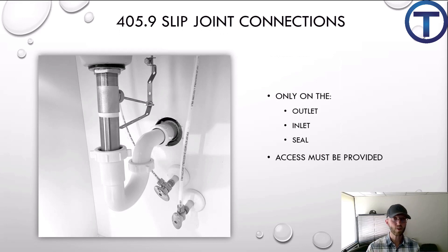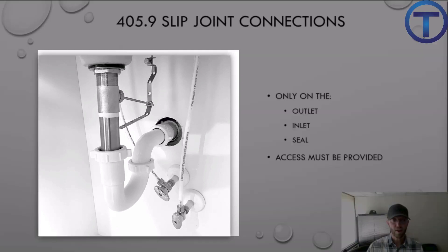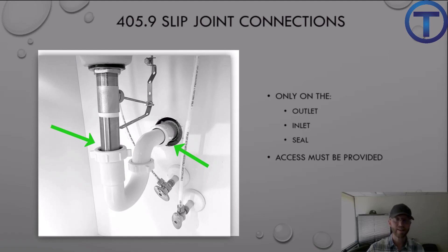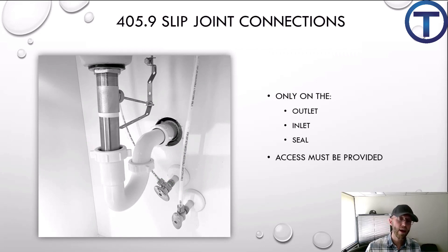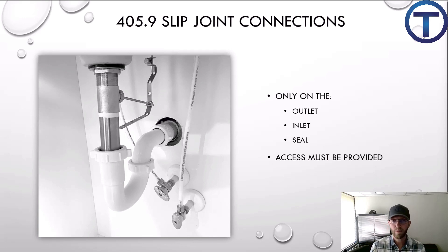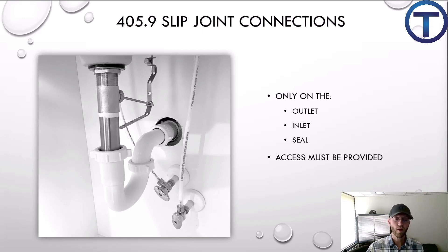405.9 covers slip joint connections, which we use all the time to connect sinks. There is a limit: you can have a slip joint connection on the outlet — that's the back by the wall — on the inlet where it connects to the tailpiece, and within the trap seal. With kitchen sinks or bathroom sinks, we may expand that slightly with disposal waste, continuous waste, or an extension. But beyond what's accessible within a cabinet, we are not to install slip joint fittings inside walls. Anytime a slip joint is used, it has to be accessible — tubs should have an access panel in the wall or ceiling.